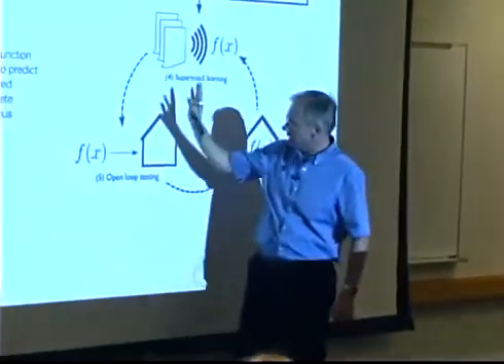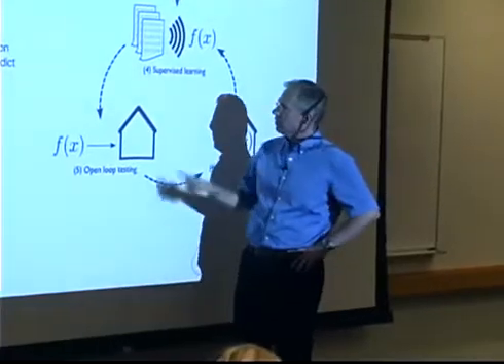And for that, we have started to investigate a new approach, which is relying on offline MPC and utilizing what we call rule extraction. So we have a building energy model, and that model we now exploit in an offline ivory tower simulation MPC approach. We get optimal results, and those optimal results we then use in a supervised learning context. In that context, we can either use discrete problem classification or regressions using continuous variables. So we have classification and regression techniques we can apply to the optimal results, and we test these new, much simpler strategies on our simulated model.